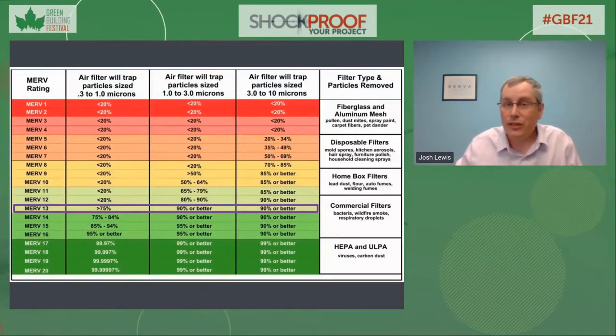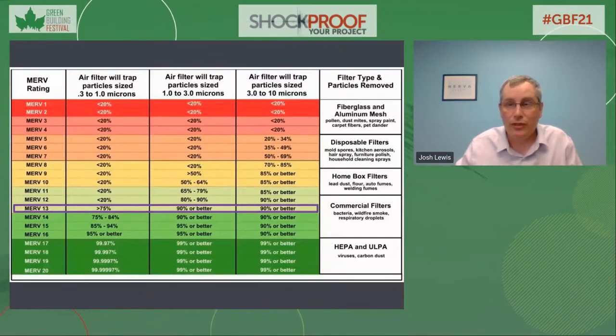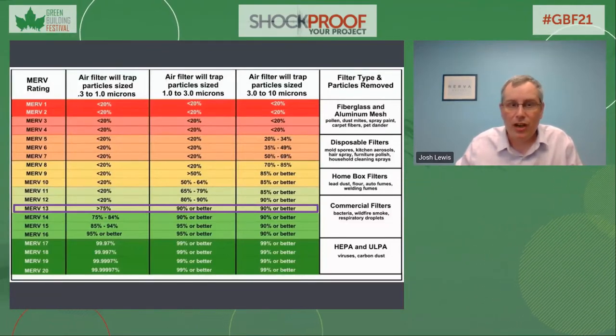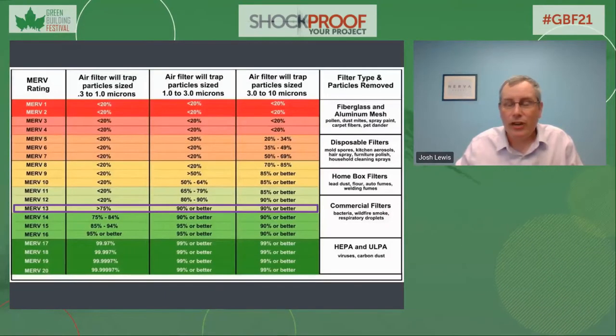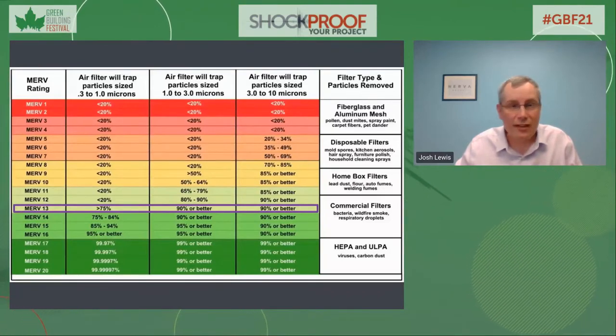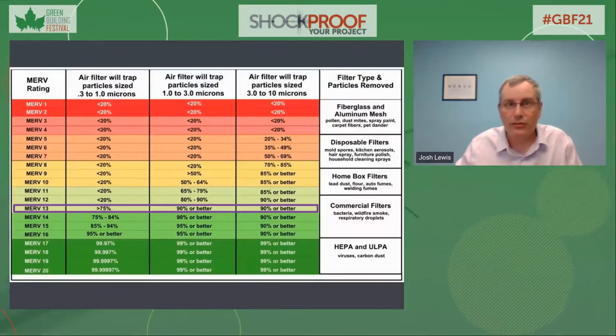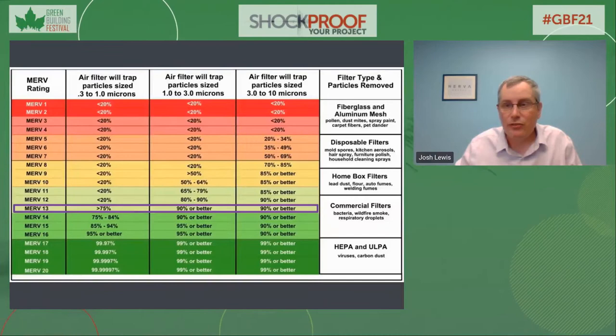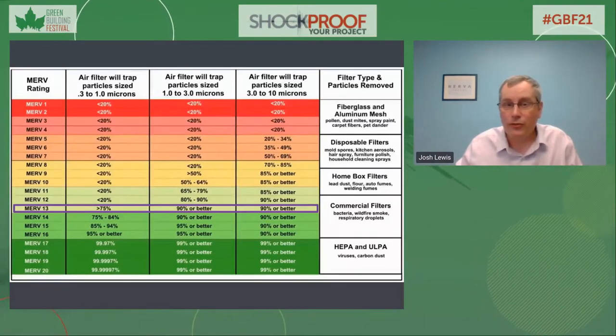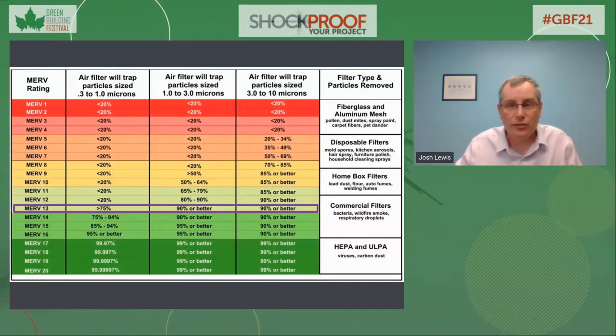Thankfully, many pieces of HVAC equipment can utilize MERV 13 rated filters by simply swapping them out, negating the need for any systematic changes. But this change comes at a cost. Filters with higher MERV ratings need to be changed more often, as they will naturally capture more contaminants in a shorter period of time. There's also the potential need for the system fan to work harder to pull air through the filters, creating an uptick in electricity usage.